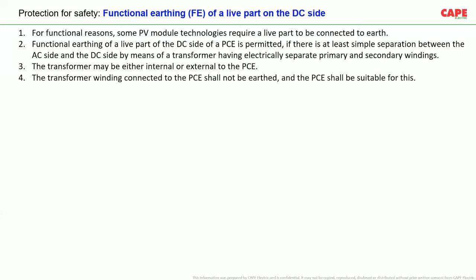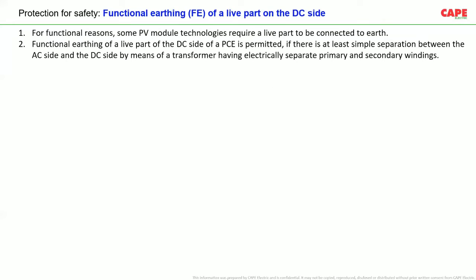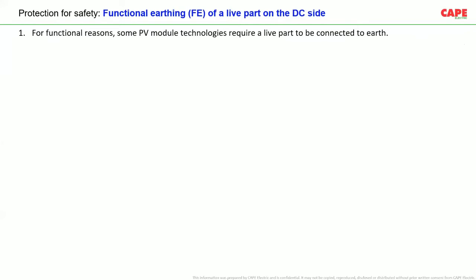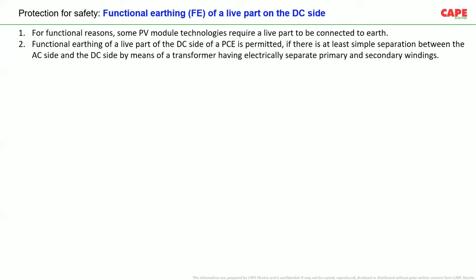If you use functional earthing, you should also note that, for functional reasons, some PV module technologies require a live part to be connected to earth. So not only the PV module, not only the inverter, the compatibility of the inverter and the PV module must be made in common. Second, functional earthing of a live part of the DC side of a PCE is permitted if there is at least a simple separation between the AC side and the DC side by means of a transformer having electrical separation. So functional earthing is possible only if you have an electrical separation, whether internal or outside.